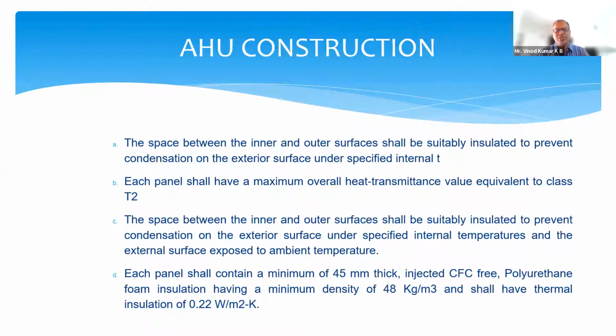So the AHU comes with a double skinned panel with an insulation minimum of 45 mm thick, and that insulation can be of various categories. It could be fiberglass, rock wool, or it could even be polyurethane puff kind of insulation that can be injected in the gap between the two panels. And its criteria is that it should be a minimum 45 mm thick, and the density of the insulation at least 48 kg per cubic meter. And here the total thermal insulation value, once you set up the panel, the vendor has to confirm that it gives you a minimum of 0.22 watt per meter square Kelvin. This is the U value. U value is the thermal insulation value of that panel in totality.